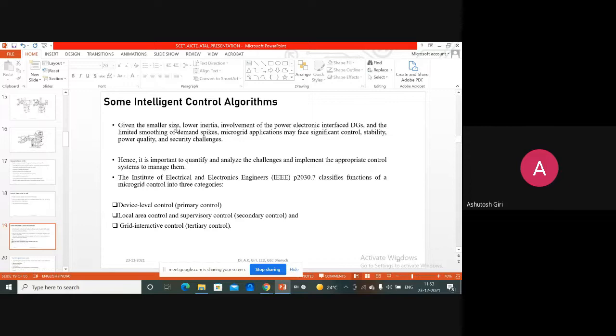But in microgrid, because of smaller size and lower inertia, all these things will fluctuate whenever any disturbance on the load comes. That's why control should be very intelligent to correct things within 1 or 2 cycles. Otherwise, what will happen if you allow the disturbance for 5 to 10 cycles? Your control, your protection system may fail, your other devices in the microgrid may fail. That's why the importance of intelligent control algorithms is there in the microgrid. It is important to quantify and analyze the challenges and implement the appropriate control system to manage them.